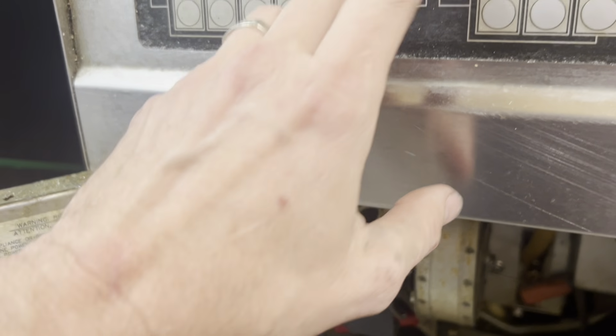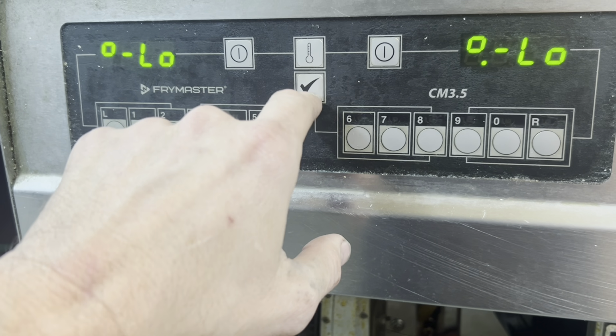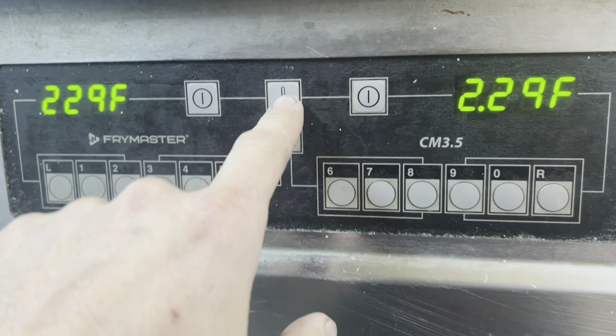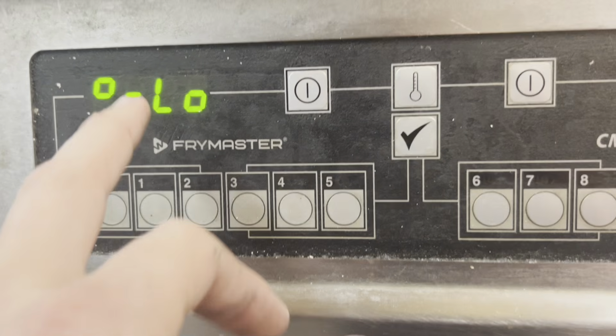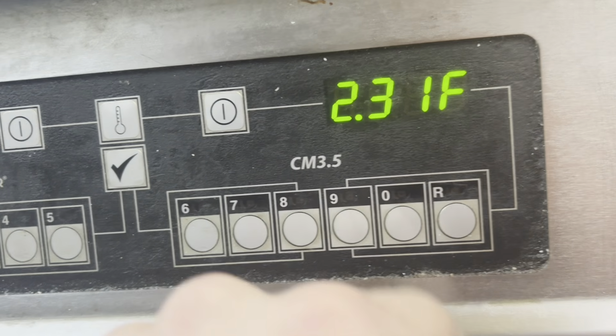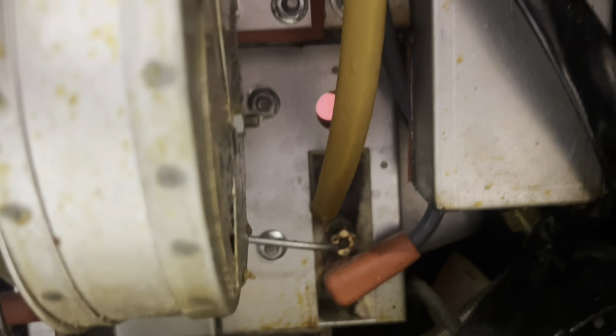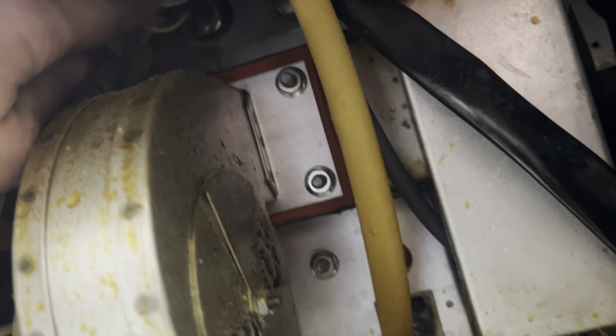The Frymaster was off when I got here, but they said that they were using it, everything was fine, and then all of a sudden it was alarming high probe, and then it was reading 515 degrees. So we're cooking now. I'm gonna go ahead and let it heat up. What that generally, when it says high probe, it means the temperature probe's shorting out. So I've got a new one, I'm prepared to change it, but I want to drive it up to temp and see what it says.